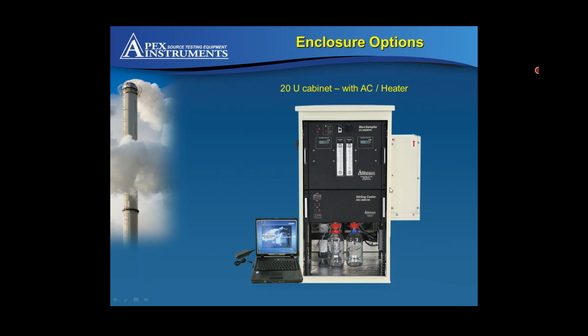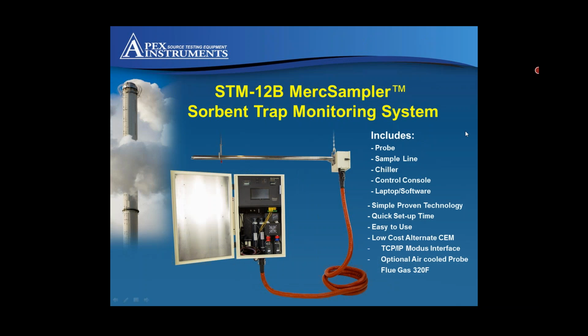It's a rack-mounted version, so you can see that the console here, the chiller, all of these are mounted basically like you would see on a rack, maybe in a trailer or a shelter. So they're easily accessible. They slide out, these types of things. Whereas you can see the STM there is repackaged in a smaller version. So the chiller's a lot smaller. Instead of being rack-mounted, the faceplate on the console swings out to give you access to all the internals if you need to do maintenance or anything like that. So that's a broad overview of the two options that we have. Again, I'll walk through how they work, but for all intents and purposes, they work in exactly the same way.